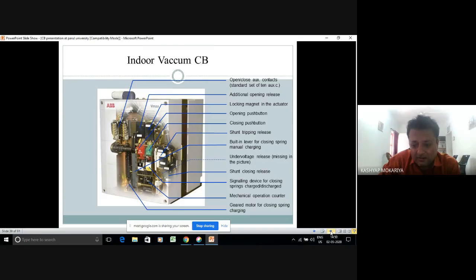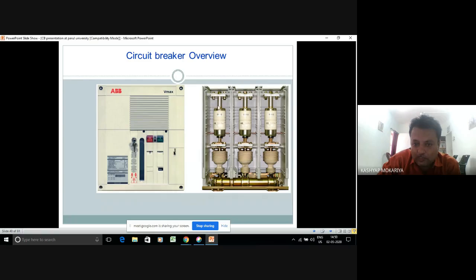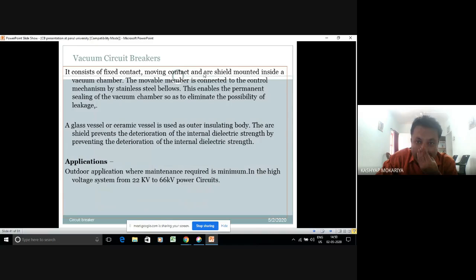It is not necessarily mentioned in the standards, because it is my view of conducting the test. Now this view will give you these vacuum bottles, how they look, and this is the assembly. The front view is there, the back view is there. It consists of a fixed contact, a moving contact, and an arc shield mounted inside a vacuum chamber. The movable contact is connected to the control mechanism by means of a bellows. This enables permanent sealing of the vacuum chamber so as to eliminate the possibility of leakage. A glass vessel or ceramic vessel is used as the outer insulating body. The arc shield prevents the deterioration of the internal dielectric strength.